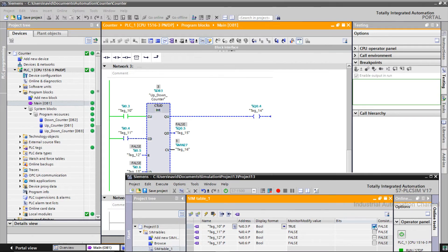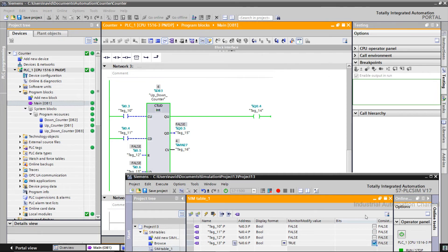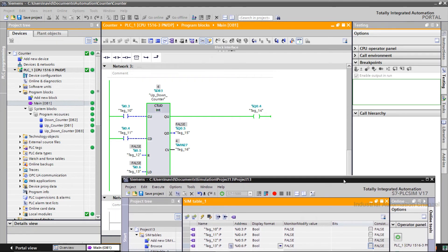Each time by pressing counter up, the current value will be increased. Now CV is equal to PV and output up is true. I make a reset — now CV is zero so output down is true. I load the PV into CV; again output up is on because CV is equal to PV. Each time by pressing counter down, CV will be decreased, and when it is zero QD will be true.